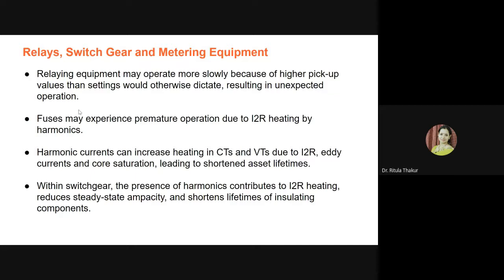You know that relays are one of the major parts of protection devices, so if they operate unexpectedly, it can lead to huge losses. Then fuses may also experience premature operation due to I-square-R heating by the harmonics. We have already seen that because of the increase in the current component, the I-square-R losses increase, and these losses basically cause heating, so fuses may also melt prematurely. Then apart from that, we have our CTs and PTs, which are current transformers and voltage transformers. Harmonic currents can also cause heating in these CTs and PTs due to I-square-R, eddy currents, and core saturation, again leading to shortened asset lifetimes.